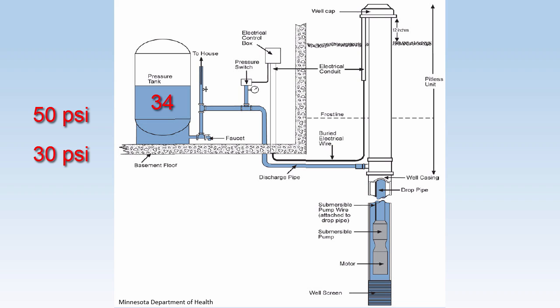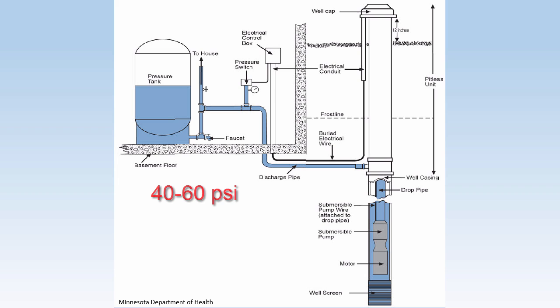The pump supplies water to your home, refills the pressure tank, and increases pressure in your system until the system reaches a preset high pressure, at which point a switch is tripped, which shuts the pump off. This is the cut-out pressure. Most systems operate with about 20 psi between the cut-in and cut-out pressure — for example, they may be set at 40 and 60 psi, or 30 and 50 psi. So your home system typically has a drop in pressure of 20 psi as water is used.